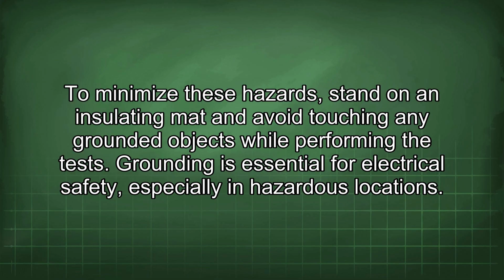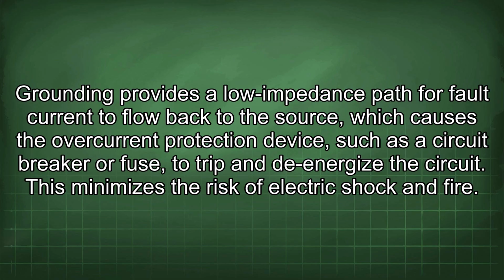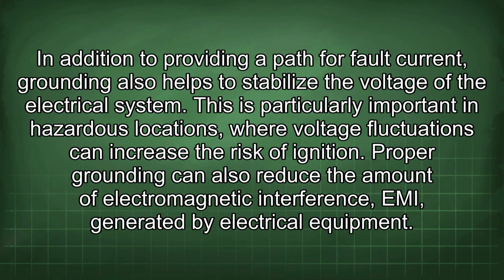Grounding is essential for electrical safety, especially in hazardous locations. Grounding provides a low impedance path for fault current to flow back to the source, which causes the overcurrent protection device, such as the circuit breaker or fuse, to trip and de-energize the circuit. This minimizes the risk of electric shock and fire. In addition to providing a path for fault current, grounding also helps to stabilize the voltage of the electrical system. This is particularly important in hazardous locations, where voltage fluctuations can increase the risk of ignition.